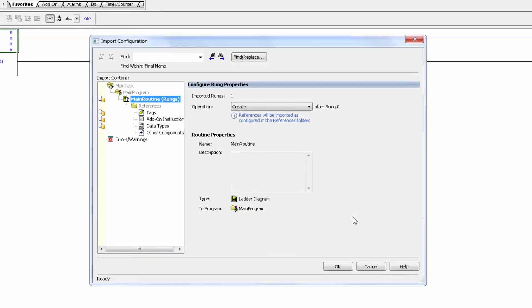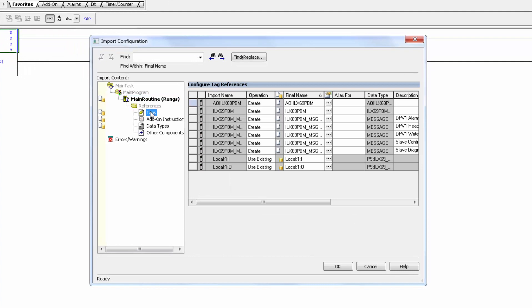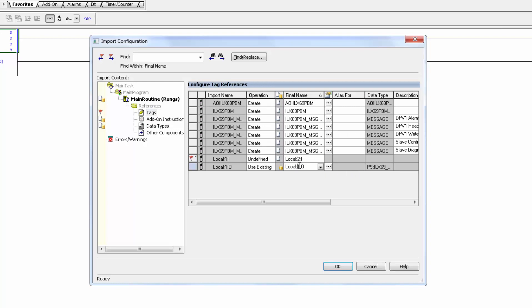To make sure this AOI or add-on instruction is pointing at the right slot number, click on Tags and make sure that the local tags match up with where the module is. If your module was in, let's say, slot 2, you would need to change these to local 2I and O. Mine is in slot 1, so I will leave it at local 1. Then click OK.